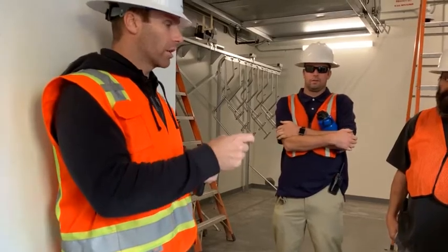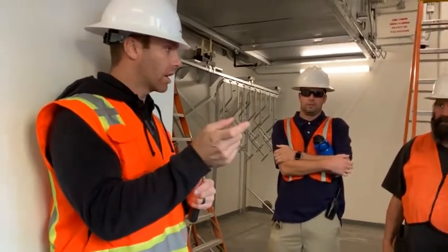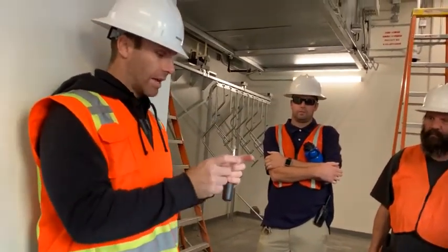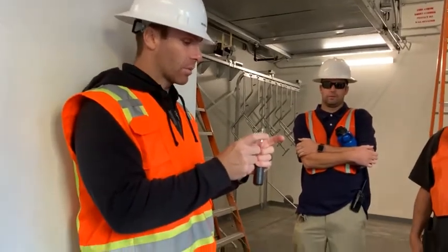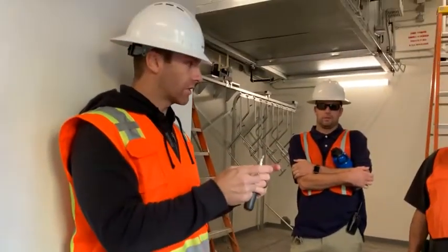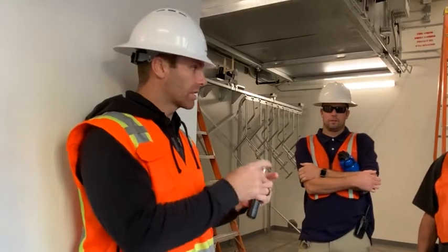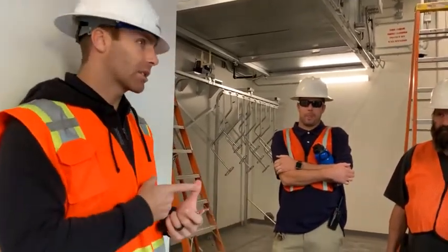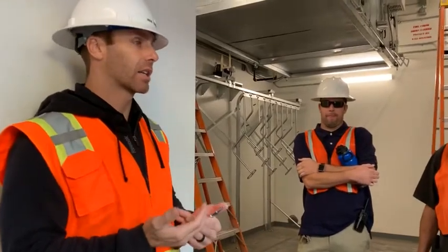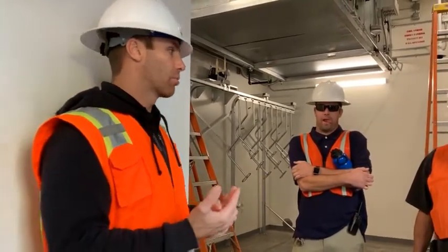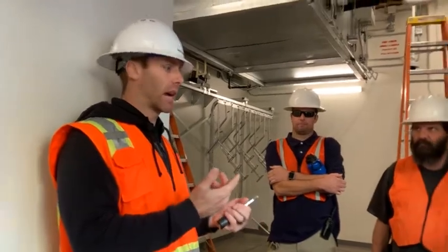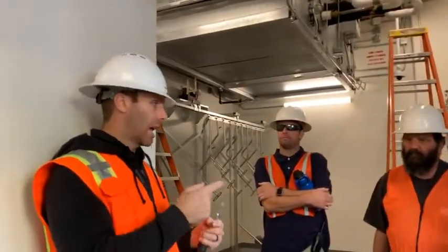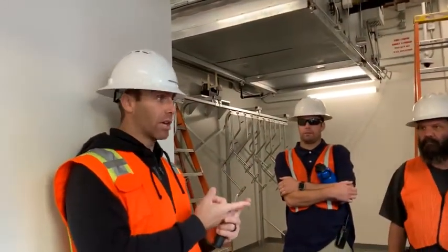So the old one will go from being online to offline, and the new one's online. And then it'll ask, hey, we lost this device, but we have this device now. Do you want to copy and replace this programming? All you have to do is hit yes. You don't have to know what settings were on there, because sometimes there are more settings changes than you realize, and you'd have to go through and literally look and know where it was default and where it is now.